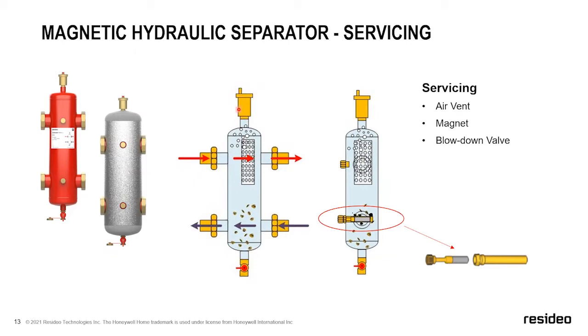Well, what's happening is that tackiness starts to assemble on top of the float assembly, which then doesn't permit that float to ride up and down as it should. So usually what I see is that float goes up a little bit, starts to come back down and sticks. So it doesn't seat all the way back. I'm actually saying that backwards. So it doesn't seat all the way up, which basically leaves this partially open. So you see this start leaking, you see it leaking water out. So we know this is a service point.